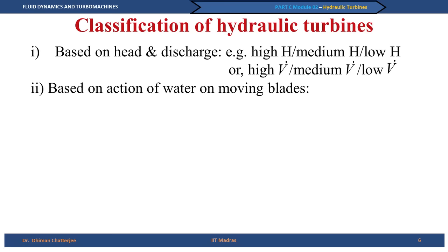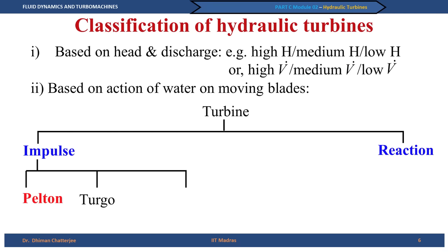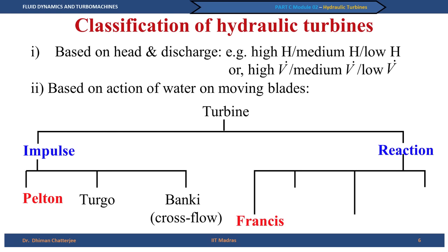Based on the action of water on the moving blades, turbines are classified into two categories: impulse type and reaction type. An impulse hydraulic turbine is one in which there is no change of static pressure in the runner blades. A reaction turbine is one in which there is a change in pressure. Impulse turbine examples include Pelton, Turgo, and Banki or cross-flow turbines; reaction turbines include Francis, Deriaz, Propeller, and Kaplan.